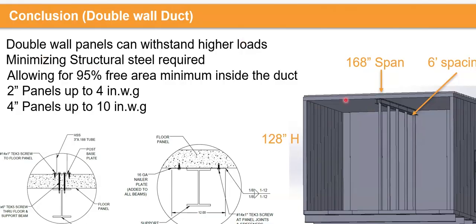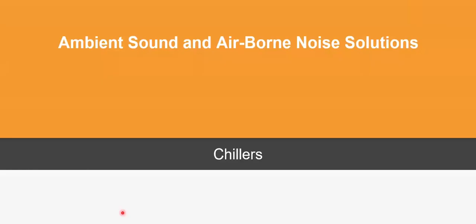that with using our acoustic panels for ductwork, you could minimize the structural steel required. You could ensure that you have the optimal free area and reduce the turbulence and pressure drop within the system. A 2-inch panel should do good up to 4 inches of water gauge, and the 4-inch panels we typically use for up to 10 inches of water gauge. I'll pass it back to Mauricio.